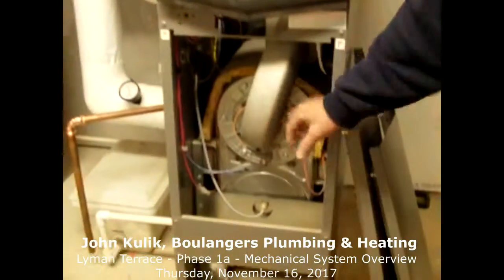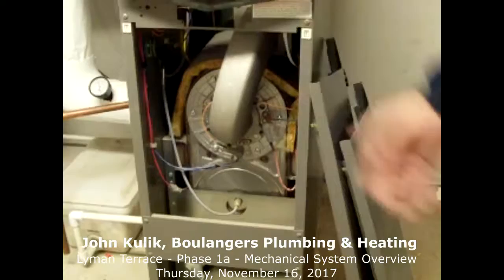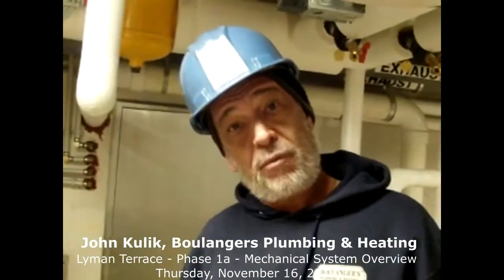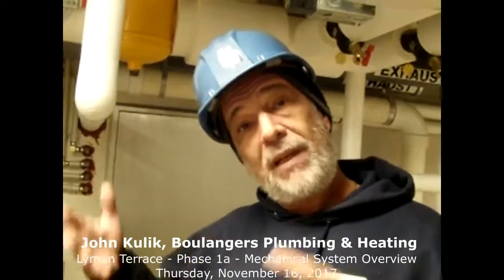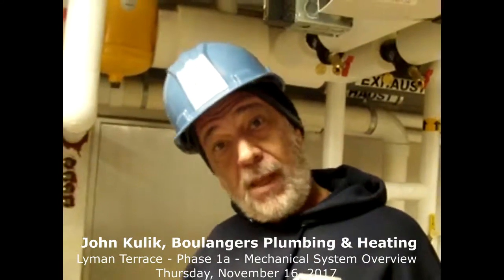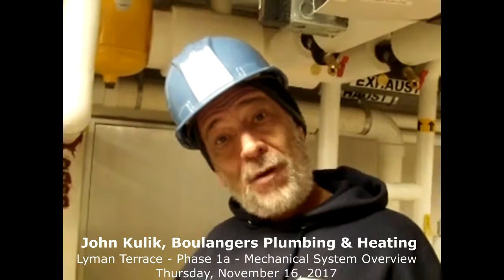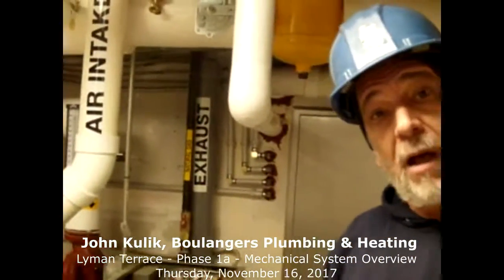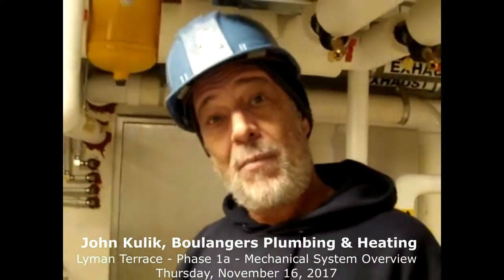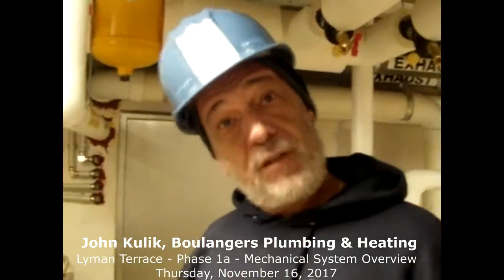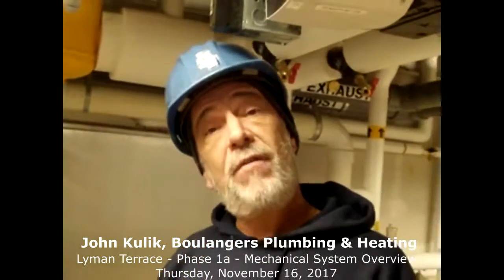This whole burner comes out. There is a stainless steel heat exchanger in there, cylindrical shape. We go in with a soft bristle brush and water, no chemical, and we clean the whole inside of that out because we need to keep the flue passages where the exhaust goes through open and clean. If those become clogged, the heat does not go into the water because it's insulated, it overheats the flue pipe leading out the back and will cause the boiler to, A, run inefficiently, and 2, it'll burn out the components faster. So service on the burner is critical to keep it running efficiently.